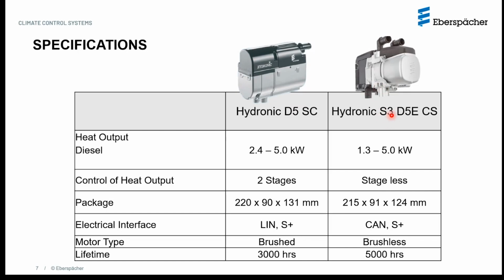3 is indicating the generation of the heater. So this is the third generation. That's why the number 3 is used. D, as I mentioned, is the type of fuel. 5 is the maximum output of the heater. And the letter E stands for economy. It's also followed by 2 letters, and this describes basically the protocol that's used by the heater for communication. So C stands for CAN bus, and the S stands for S plus, or the analog signal, 12-volt signal that could be used to activate the heater. So that's the description of the heater.